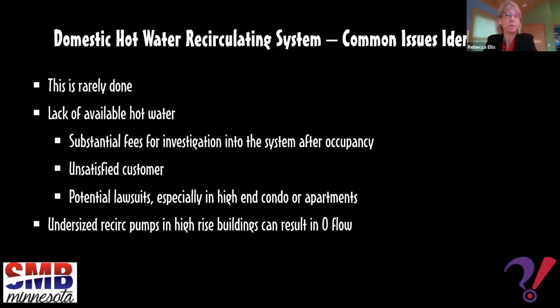If you don't have enough pump to push through the system, no type of balancing valve will work, including these. But over time, they will fail. They're mechanical devices and they will fail and you'll start having problems. And as Mark alluded to, there's no way of figuring out where the failures have occurred. You can't measure the flow across these devices. All you can do is really go up with an IR gun and measure the temperature of the pipe to see if they're actually working.